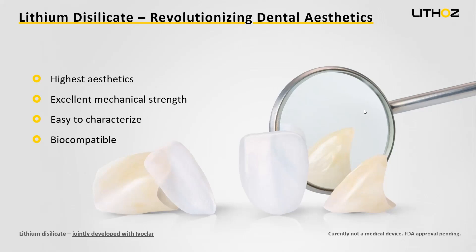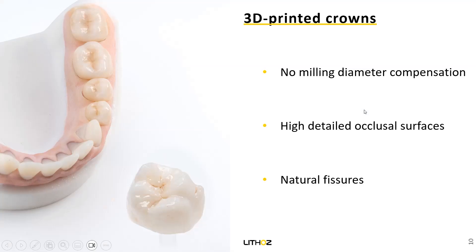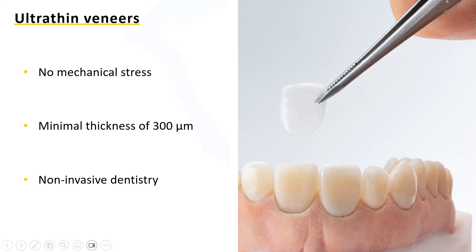Here are some 3D printed crowns and claims of our technology. A big advantage is we have no milling tools and no diameter compensation, which leads to very high-detail occlusal surfaces and very natural fissures. One of our biggest advantages is that you can print ultra-thin veneers with our technology. Since we do not use any tools, we have no mechanical stress, so we can go down to very thin wall thicknesses — down to 300 microns — which leads us to non-invasive dentistry. That should be the goal when we talk about aesthetics, because for dentists, nothing is better than avoiding grinding a healthy tooth for a veneer.